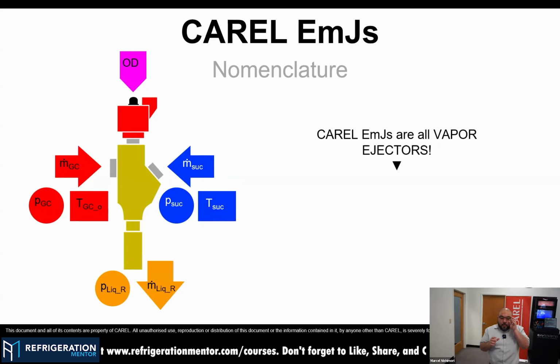The ejector, in our case, is a device that lets us take a positive effect from the refrigerant at higher pressure. When you have a refrigerant at higher pressure and higher temperature and you need to expand it, you can speed up the refrigerant inside this device, the ejector. And when we have a refrigerant at higher speed, you also create what we call a low pressure zone, a zone inside the ejector where you can create a lower pressure and start dragging refrigerant from the medium temperature area. If you see here in the picture, we have the three main components.